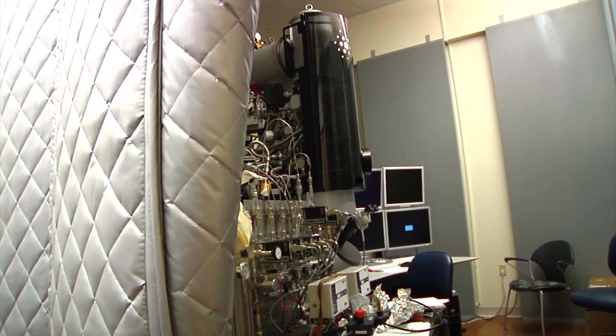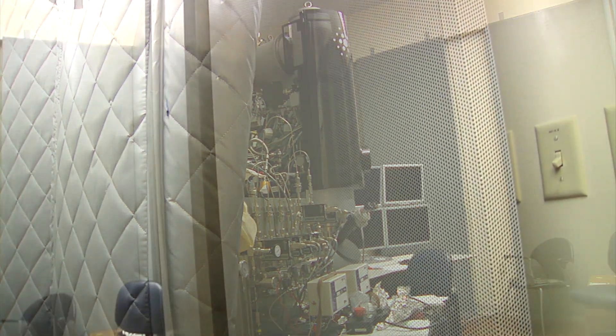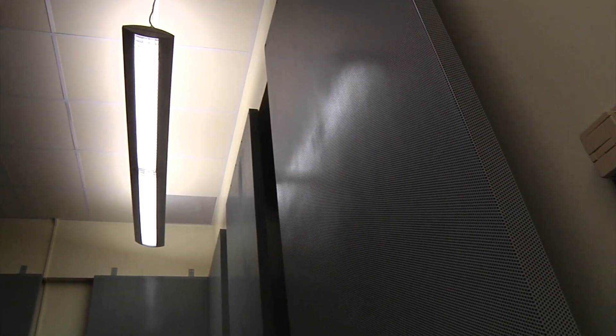We used a cork floor. We have curtains hanging around that are sound-absorbing curtains, and that keeps it very quiet in that room. We channeled the airflow so there's no temperature differential across the column of the microscope — very nicely tailored for that particular instrument.